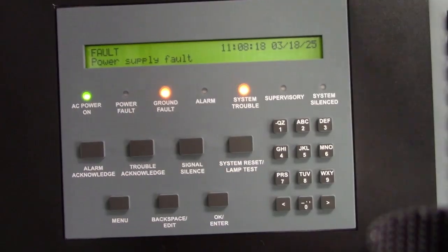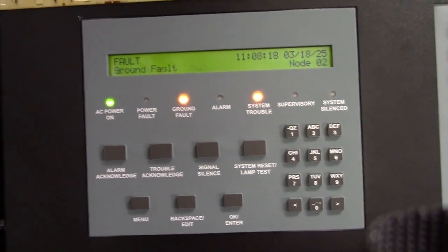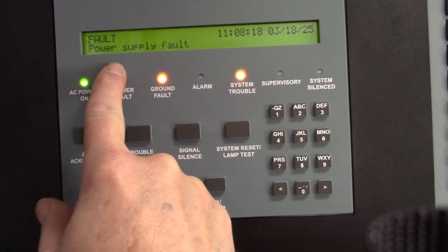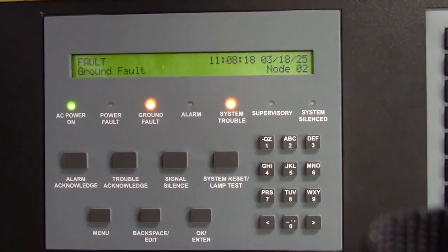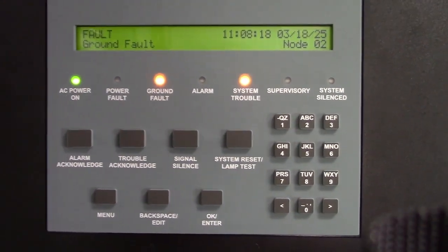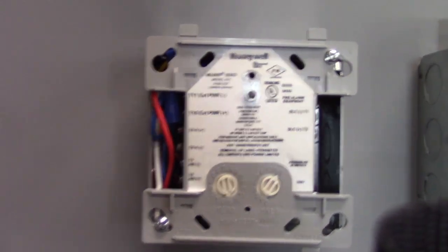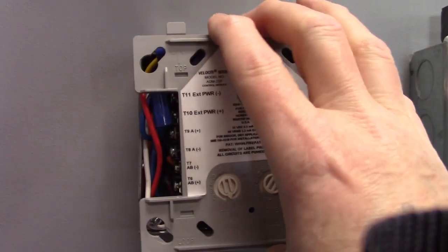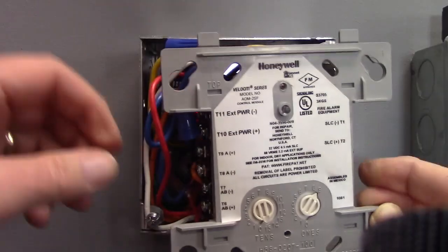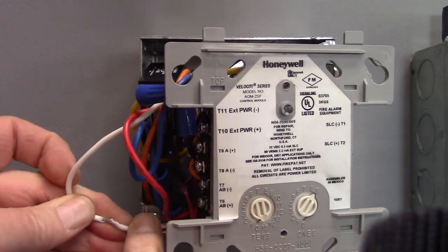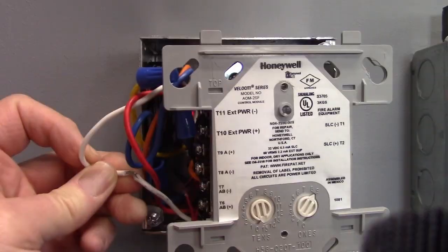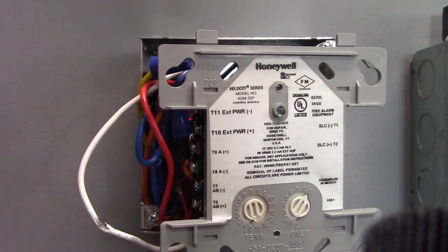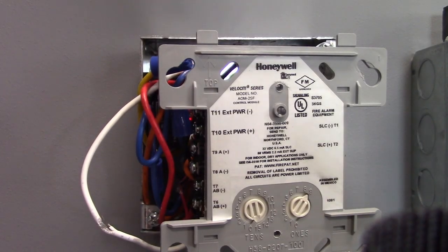Here's another system that is currently indicating a ground fault. It's got the ground fault light and it's telling you it's got a ground fault. So what does that mean? There's a pinched wire somewhere leaking current to earth ground. If we come down and take a look at a device here, what had happened was this wire got connected around the screw and it damaged the insulation. Once the problem is fixed, we'll put some tape on that afterwards, the panel will go back to normal condition.